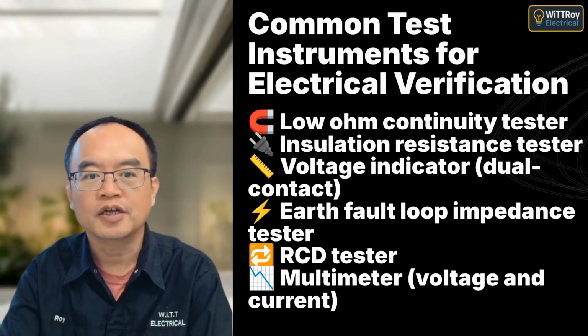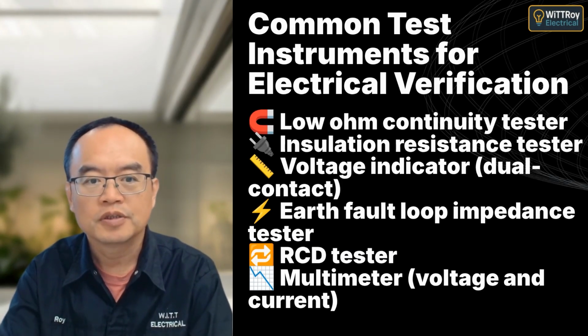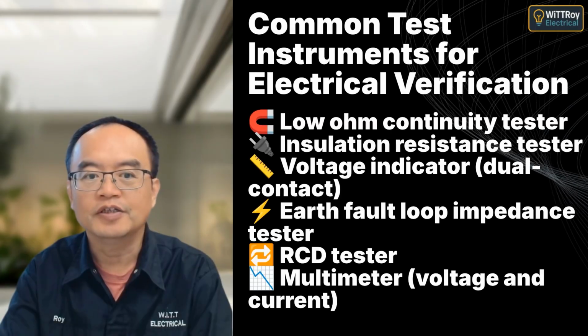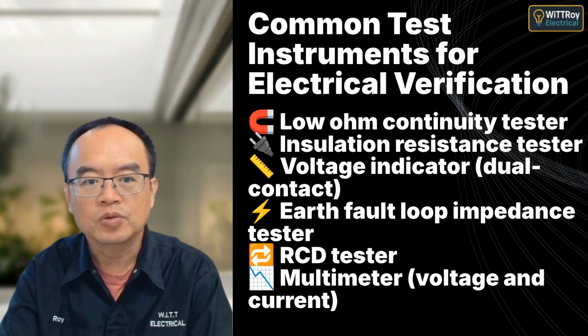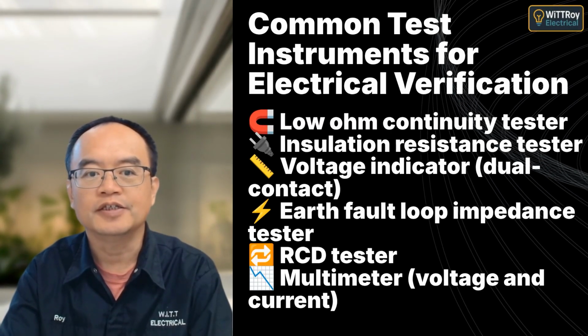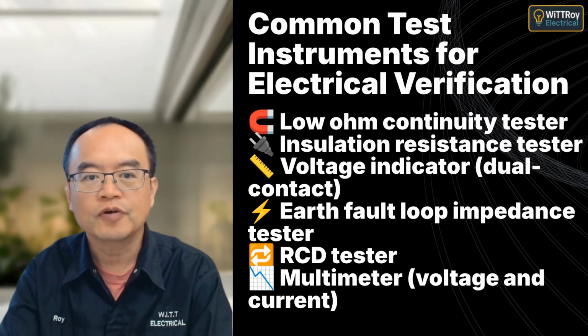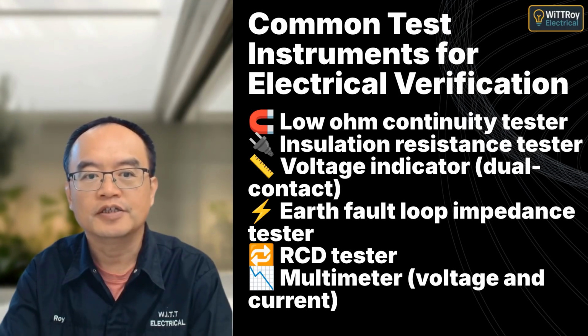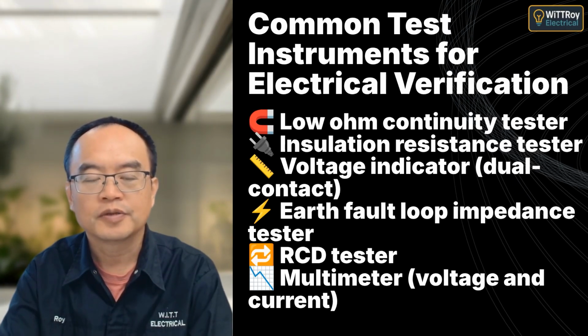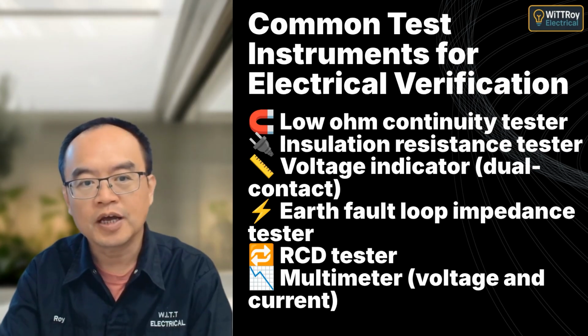Before testing any installation, make sure you're using the correct instruments. AS/NZS 3017 lists the essential tools for verification: continuity testers, insulation testers, voltage indicators, RCD testers, and more. Each test has a purpose, and the right tool ensures reliable results.